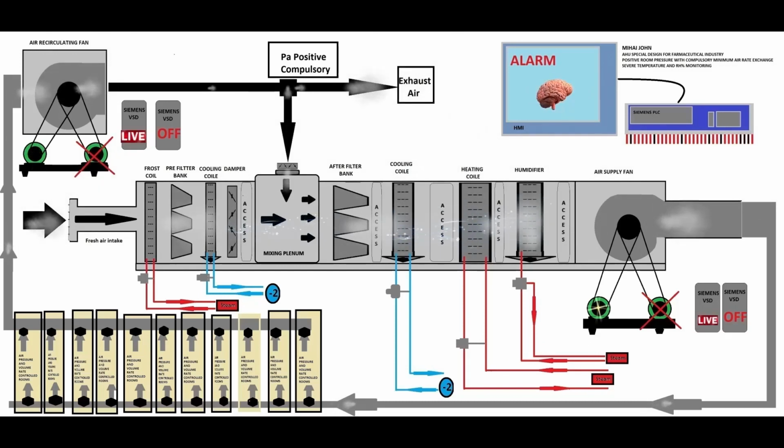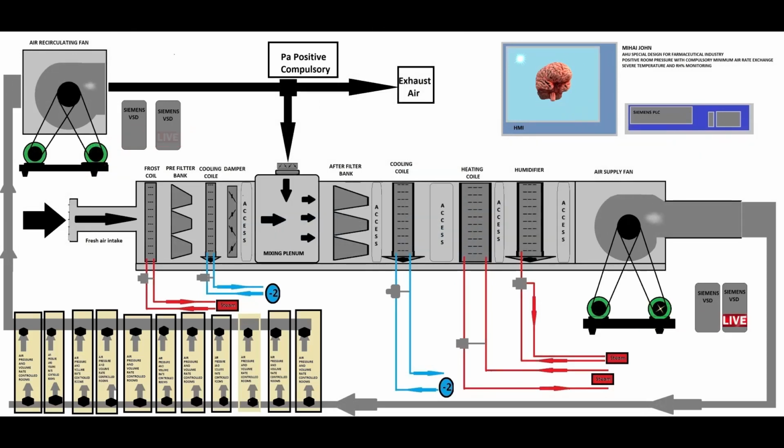So this system runs well, but you still have an alarm now, as you'll see, and that alarm will only disappear if you repair fan number 1. As you'll see now, motor number 1 runs and inverter number 1 runs. It's live again. Because you don't have any fault, you don't have any alarm.